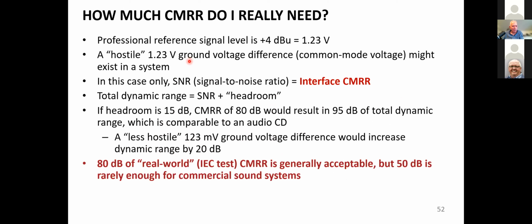The signal to noise ratio will actually be equivalent to the common mode rejection ratio if you're in a fairly hostile environment where you might see 1.23 volts of ground voltage difference, or +4 basically. But if you're in a less hostile environment where you may have only 120 some millivolts of ground voltage difference, then you could use 20 dB less common mode and get away with it.